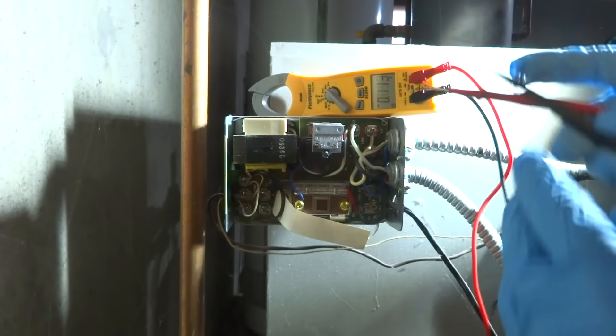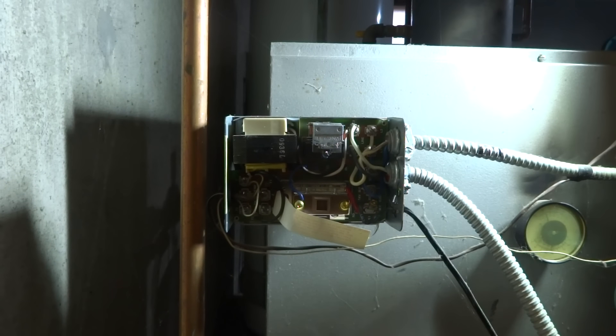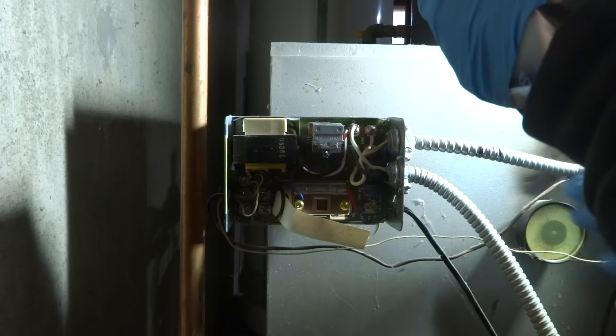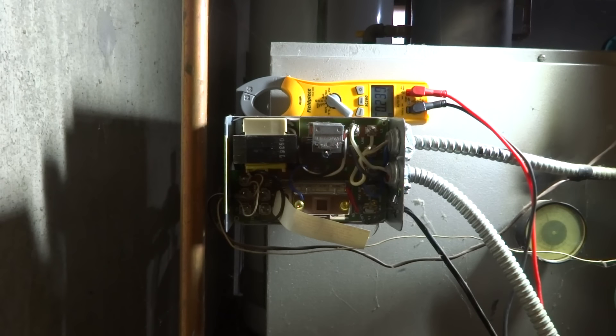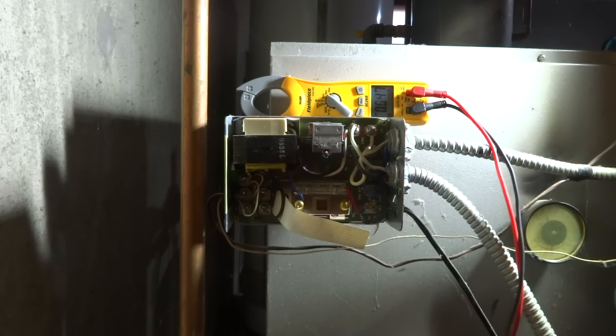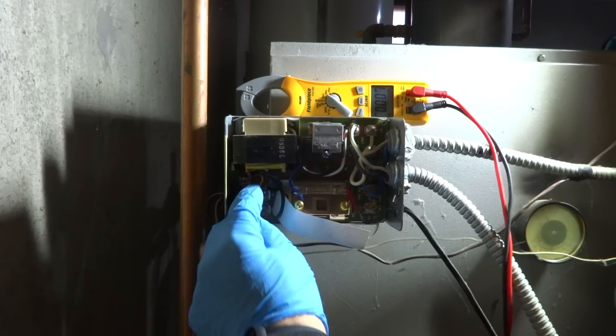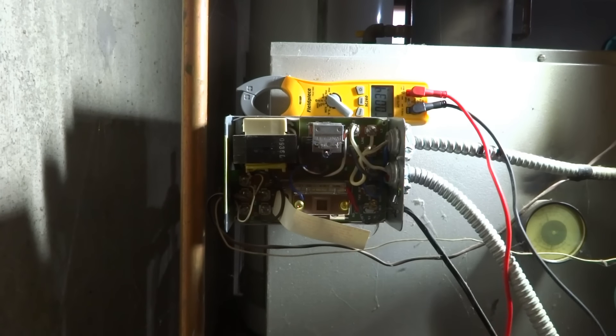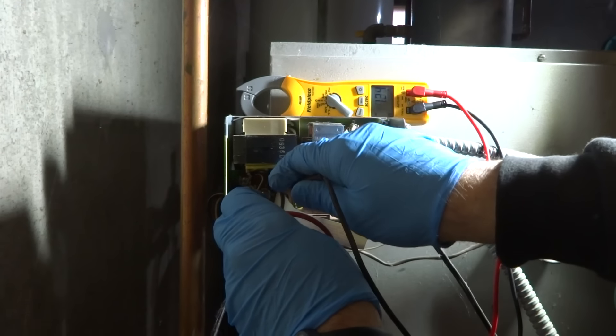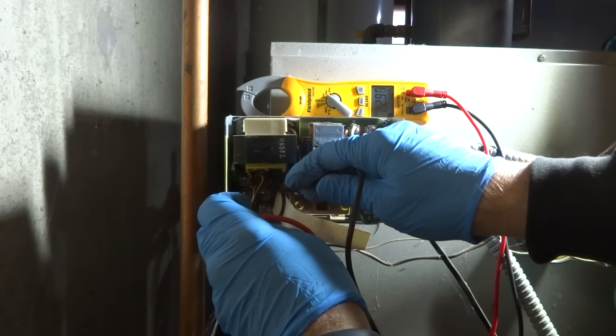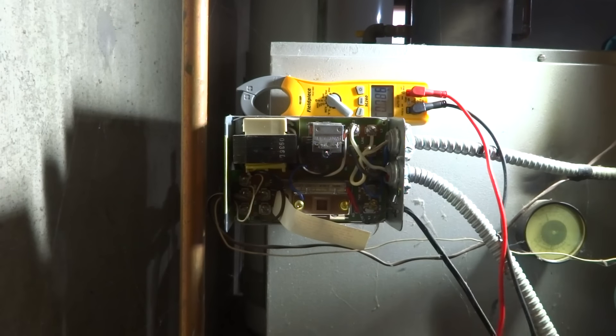C1, C2, no voltage. Alright, so we got a control. Let's put another control in there. See if I got voltage coming in on the transformer to run those zone heads. We got 25 volts. It's a bad control. Let's see if I got 24 volts here on this control. We should. Was it the transformer that's bad? Nope. The control's bad.